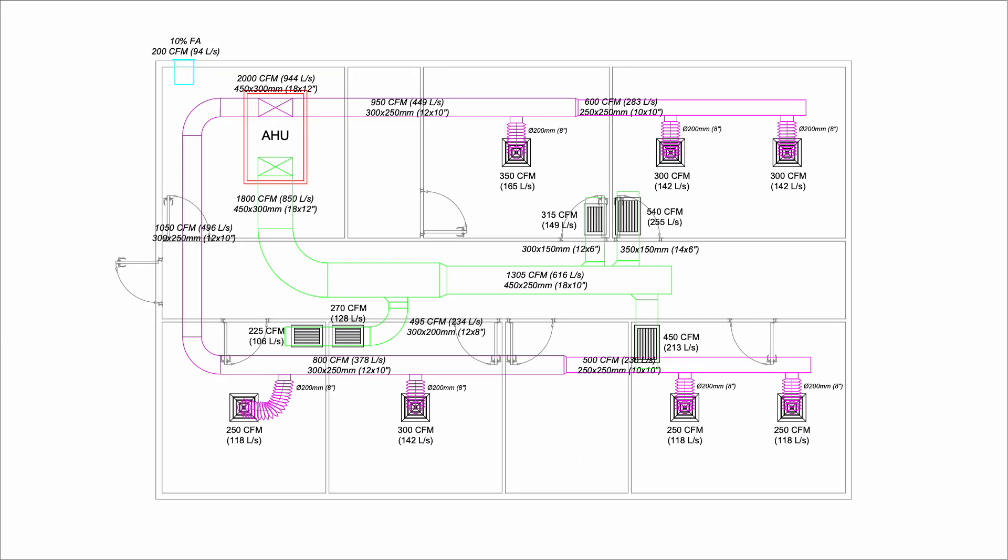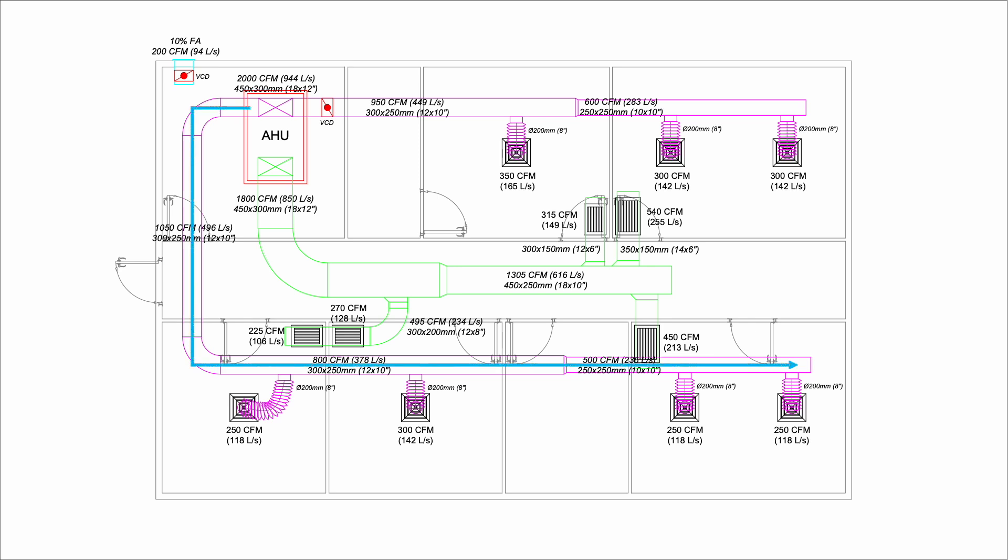Between the two supply ducts, this route has more static pressure. Air tends to flow toward ducts that have less static pressure. Therefore, we need to block some of the air at the shorter path to get enough airflow into the longer path. As for the fresh air damper, we want to control precisely at 10% only.